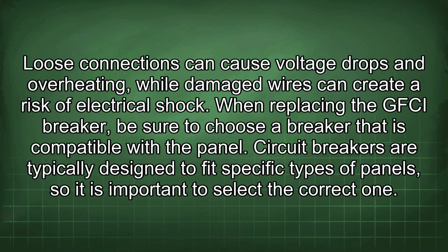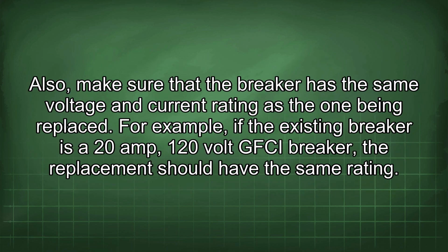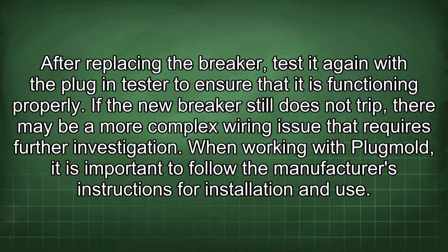When replacing the GFCI breaker, be sure to choose a breaker that is compatible with the panel. Circuit breakers are typically designed to fit specific types of panels, so it is important to select the correct one. Also, make sure that the breaker has the same voltage and current rating as the one being replaced. For example, if the existing breaker is a 20 amp, 120 volt GFCI breaker, the replacement should have the same rating. After replacing the breaker, test it again with the plug-in tester to ensure that it is functioning properly. If the new breaker still does not trip, there may be a more complex wiring issue that requires further investigation.